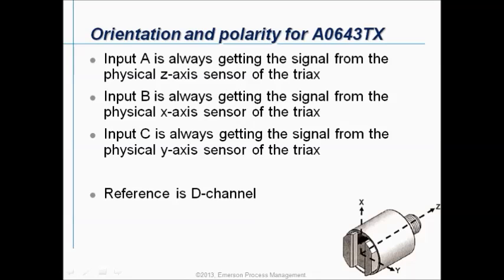One of the benefits of using the CSI 2140 Machinery Health Analyzer is that this is a 4-channel analyzer. ODS or modal jobs can be done with the use of a triax sensor, and the recommendation is to use the Emerson triax sensor AO643TX. When you connect this sensor, input A always gets the signal from the physical Z axis sensor of the triax — that's your channel A. Input B always gets the signal from the physical X axis sensor of the triax, so this is always your B.